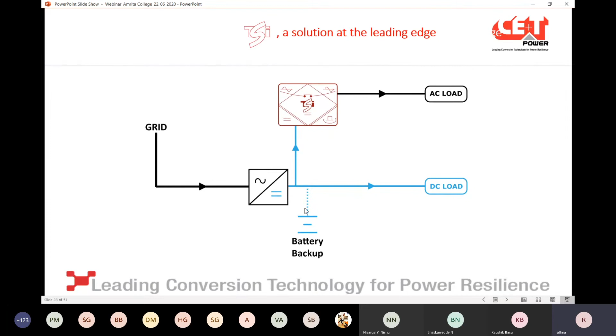Comparing to a UPS: in a traditional system you have the rectifier, batteries, and charging, plus a separate UPS, requiring separate batteries for the UPS segments. You oversize to bring redundancy, the AC branch is not expandable, and you need a critical maintenance contract for the UPS.